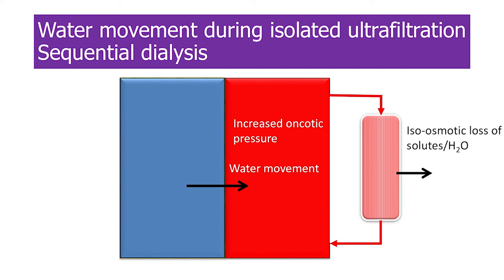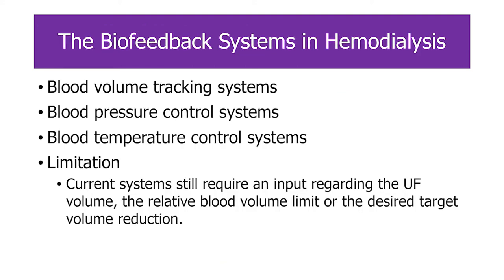Isolated ultrafiltration with removal of iso-osmotic fluid increases oncotic pressure in blood, causing movement of water from the interstitial to the vascular compartment. You can use isolated ultrafiltration — sequential dialysis: ultrafiltration with no dialysis followed by dialysis with no ultrafiltration. Biofeedback systems, blood volume tracking systems, and blood pressure control systems have been developed, but they still require operator input regarding target blood volume limits and desired fluid removal.